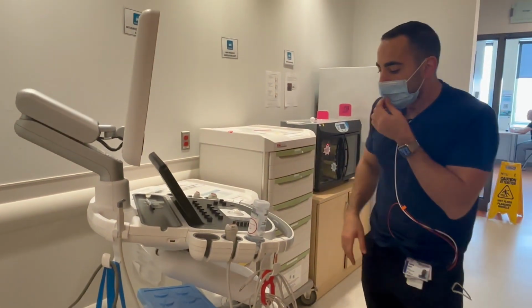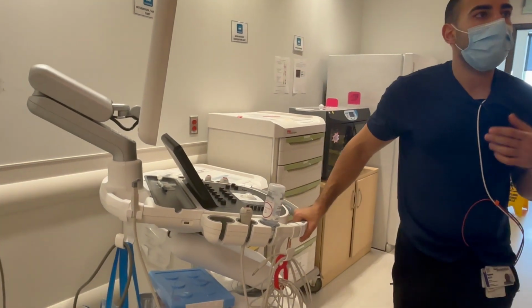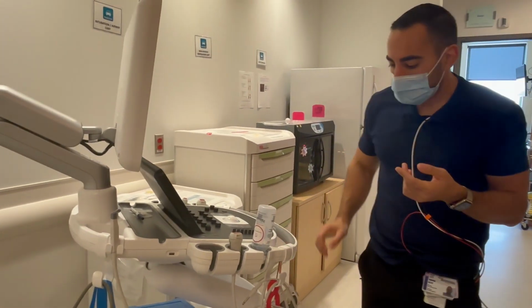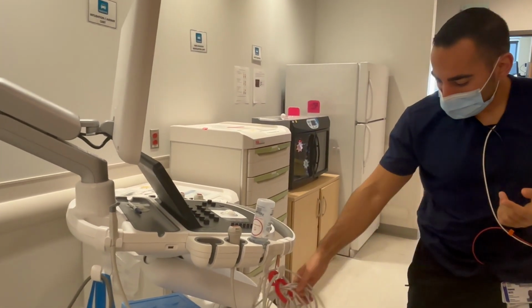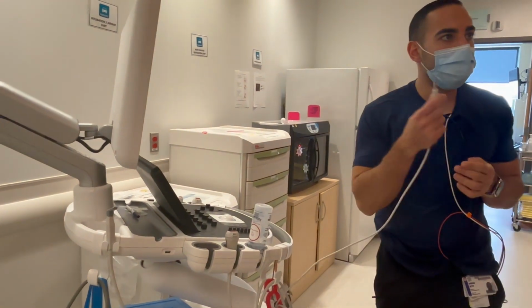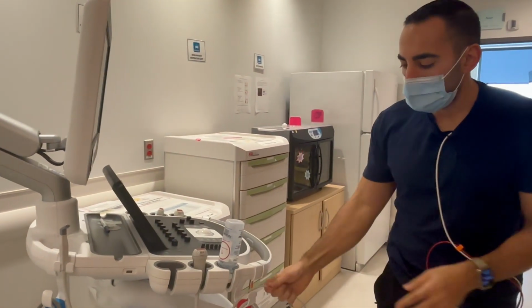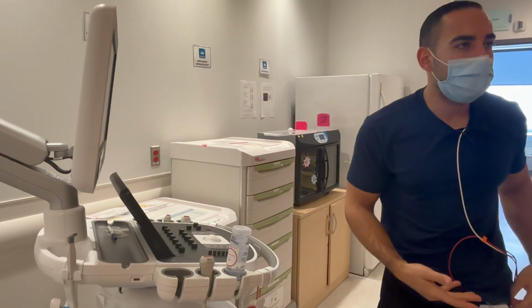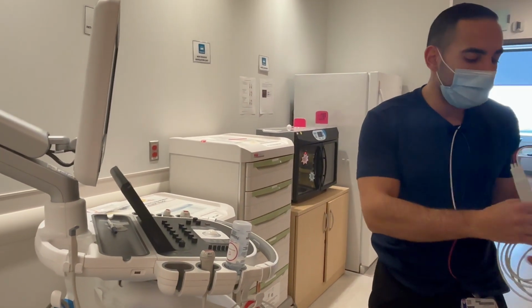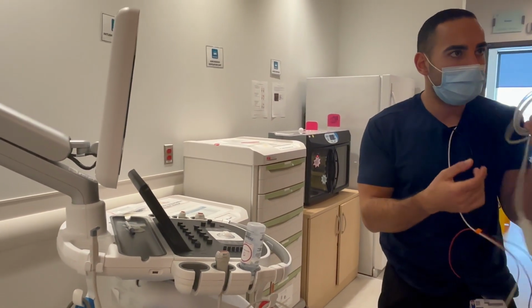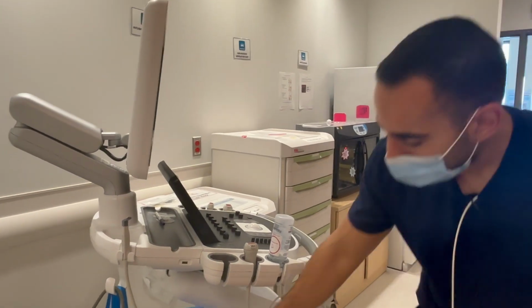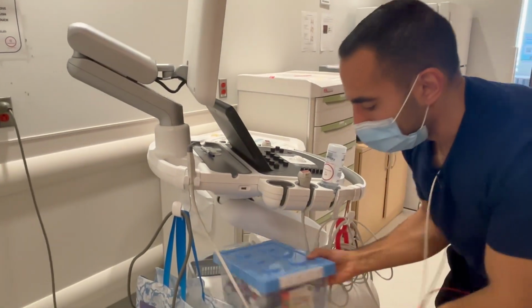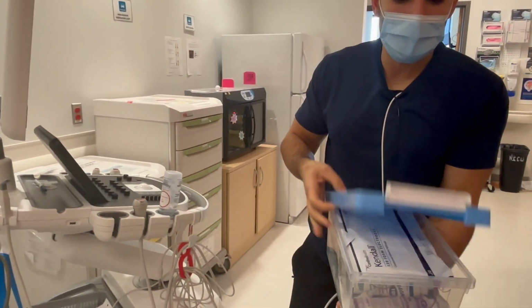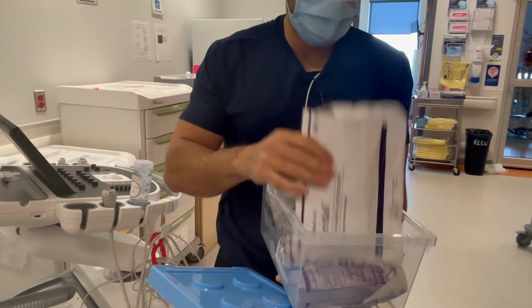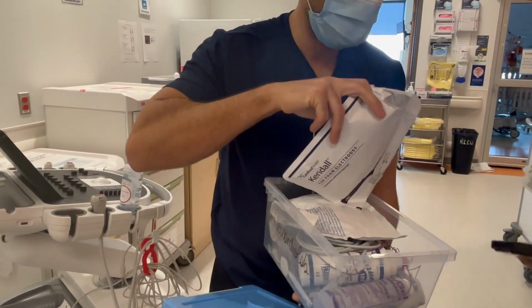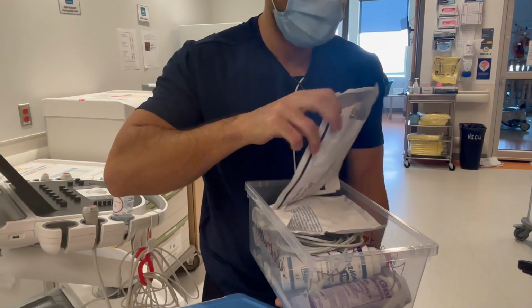Okay. The echoes have to be done ECG gated. Typically on the machine, what's attached is the auxiliary ECG that attaches to monitors. Ideally, you're going to have a lot of outpatients, so we're going to use the adult ECG capturing device, which typically is in the box that is on top. And in this box, you will find foam electrodes. These are the foam ones that we use mostly for pediatric. They're not great for adults.